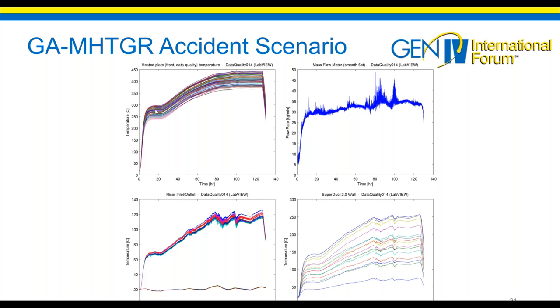This is basically what we call a horsetail plot that shows all the data. You'll see that the peak temperature, based on the scale testing, is quite close, about 440 degrees, to what was predicted by the designers for this system a number of years ago, and that was occurring at about 120 hours, as predicted. It might have occurred a little earlier, but after about 100 hours you're basically stabilizing at about what the designers thought the system would evolve to.